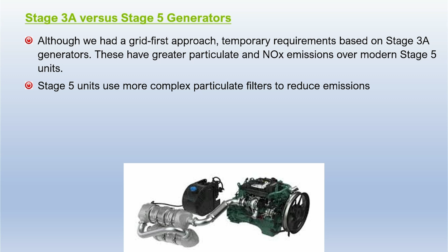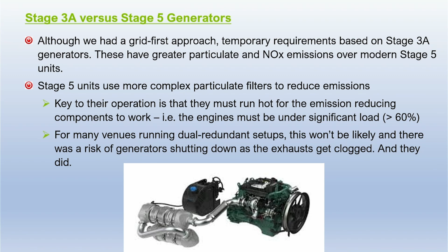The Stage 5 Euro emissions compliant engines actually need to run hot in order to work the catalyst and the exhaust - I'm not quite sure how exactly they work - but they've got to be under significant load, more than 60%. So automatically that rules out your plain twin set generator model, because if you don't load them up properly, they run inefficiently and shut down. We can't have generators turning themselves off because they don't like their exhausts getting clogged up, which is the whole reason for the Stage 3 requirement in the first place.